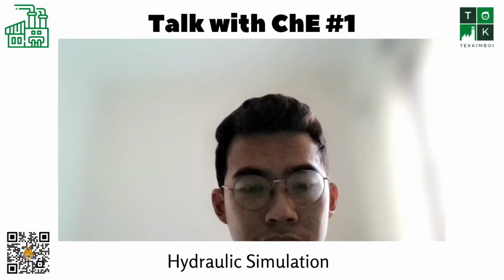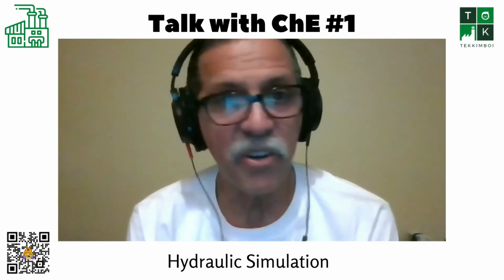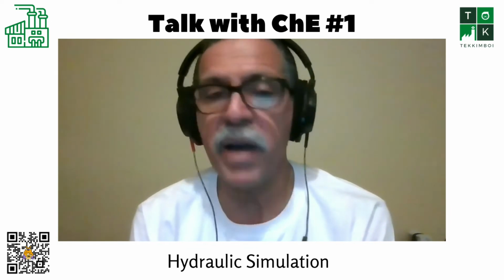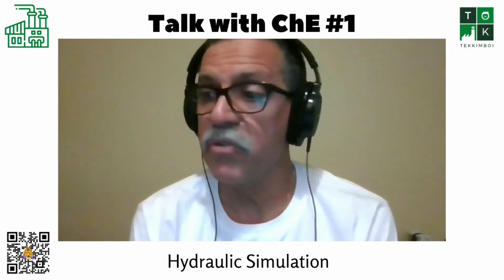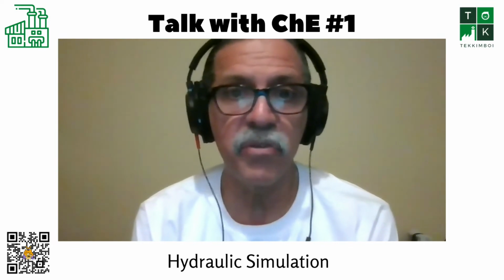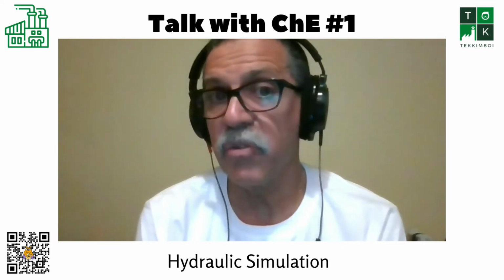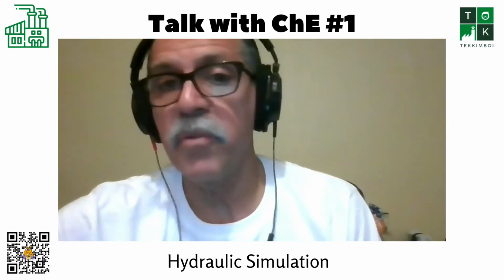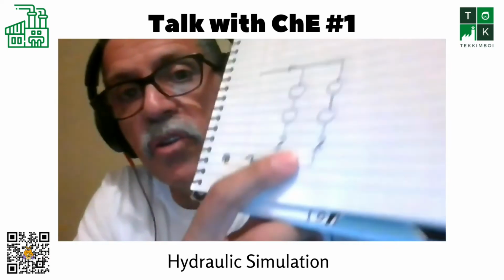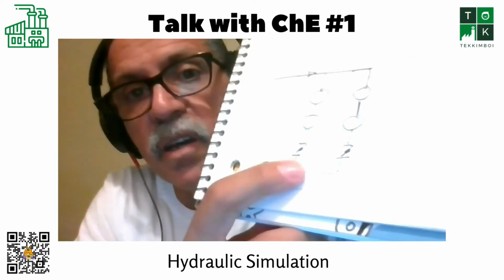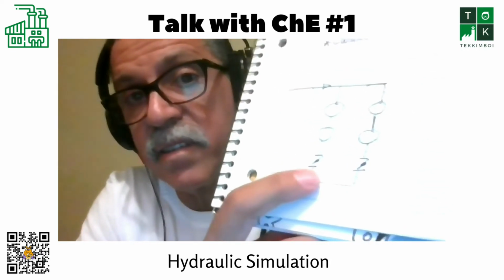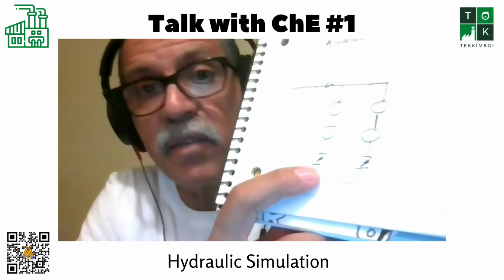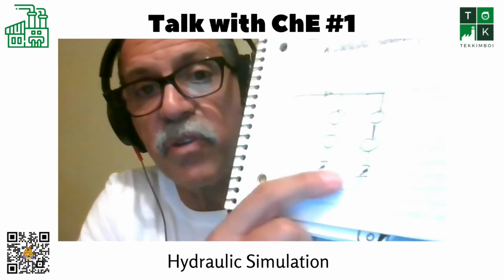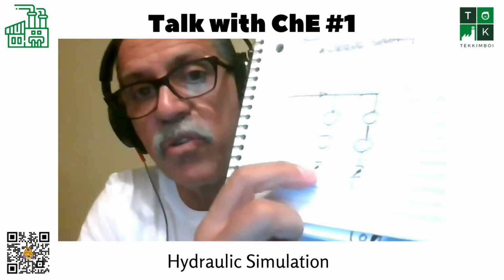They said, no, the problem is not the pipeline size. The problem is not the condenser. The problem is the piping arrangement that needs to be upgraded. And when you run this simulation, the simulation can give you some ideas or some problems. I remember that one of these nodes was not balanced, so it was giving negative pressure, as if the flow rate was going that way or that way.